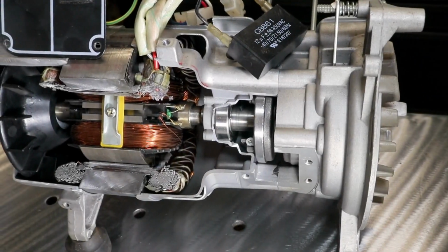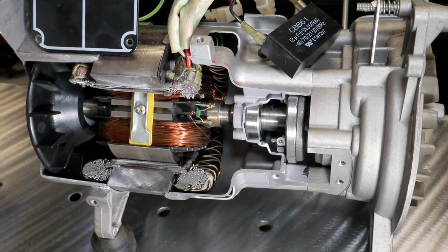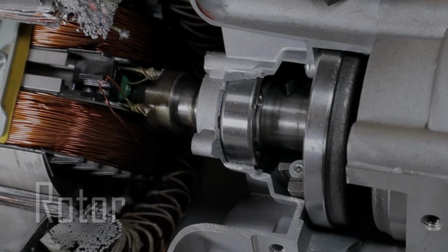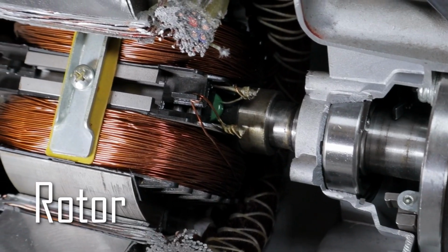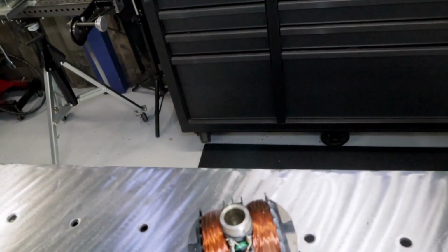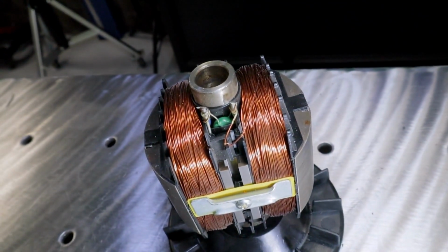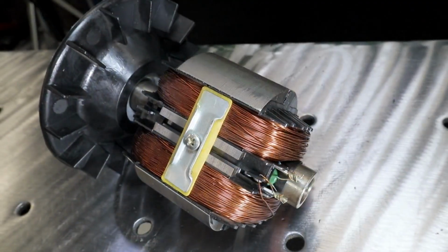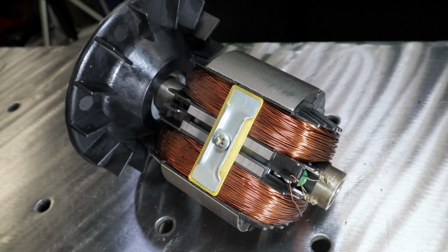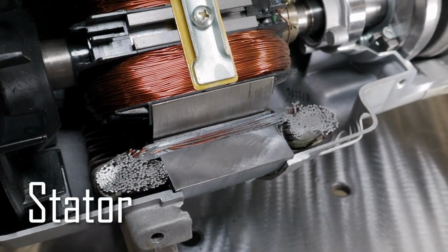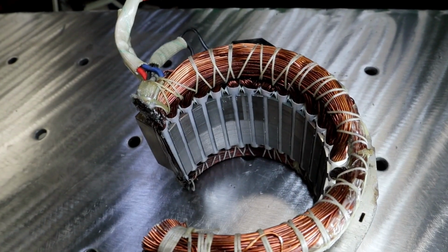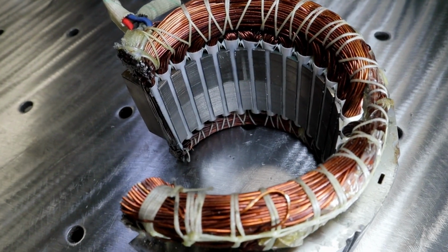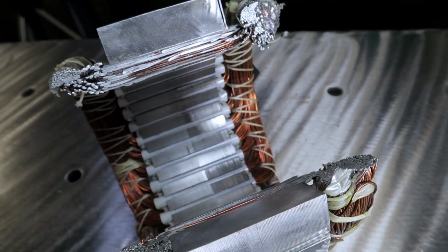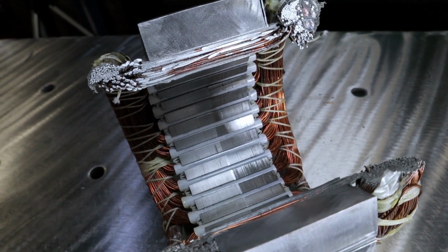All right, let's look at some of the components that make up the generator. Two main ones. We have the rotor, the rotating part, typically an electromagnet or permanent magnet that creates a magnetic field. It's driven by an external mechanical force, whether it's a turbine engine, wind, in our case, gas powered. The next component we have is a stator, or the stationary part, and it consists of conductive coils or windings arranged around the rotor. The rotating magnetic field induces an AC voltage in these coils.